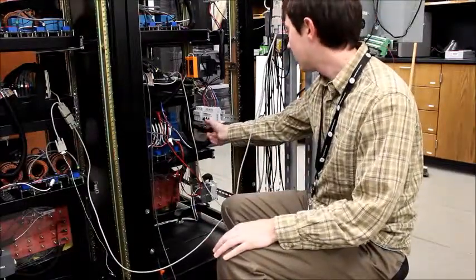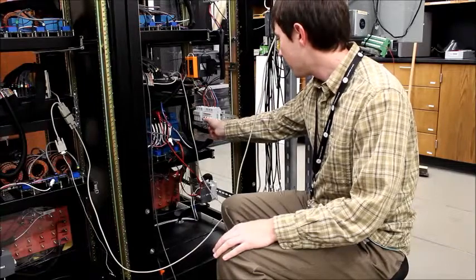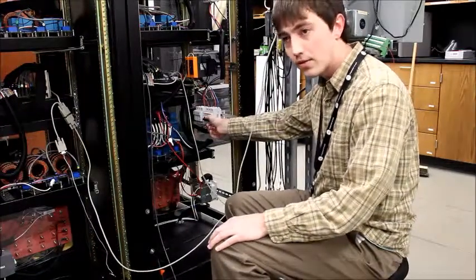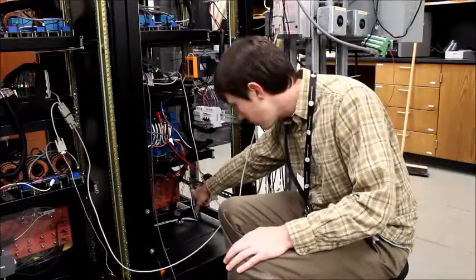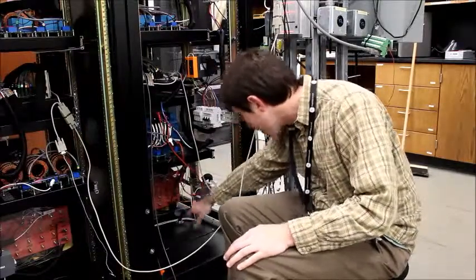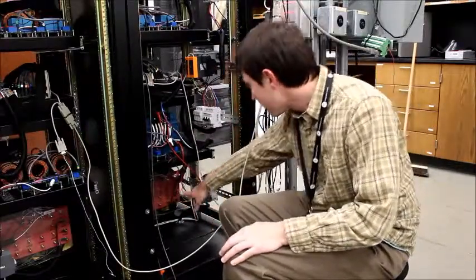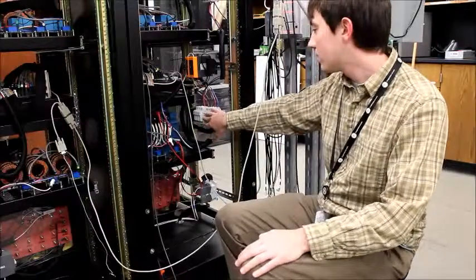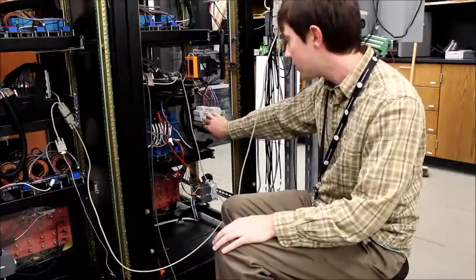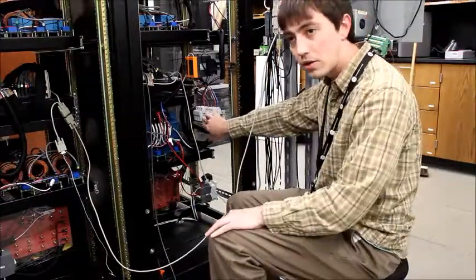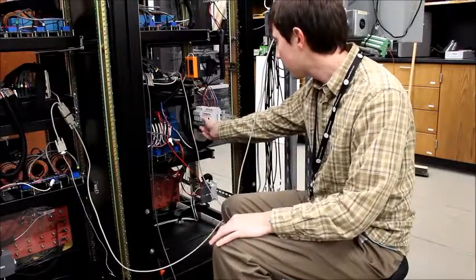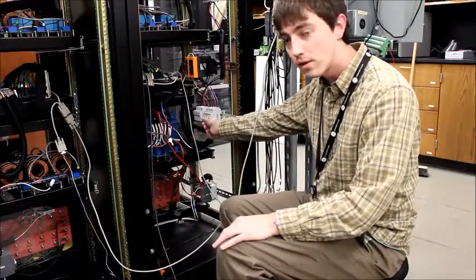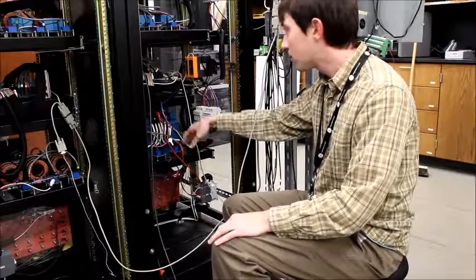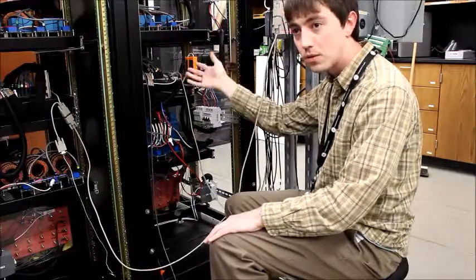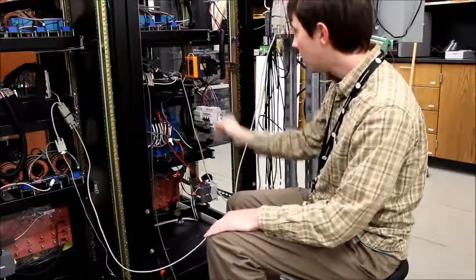the converters powered. This contactor controls the input to the active front end, which comes straight off the transformer secondary. So the transformer secondary goes to this breaker, which goes to the input to the active front end.